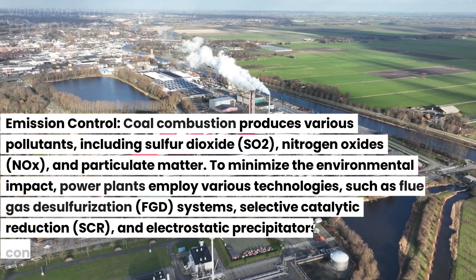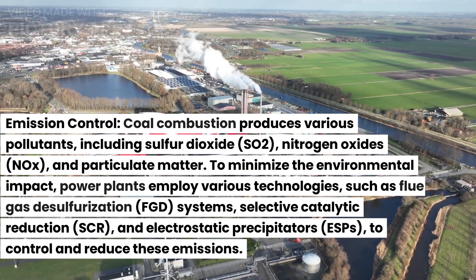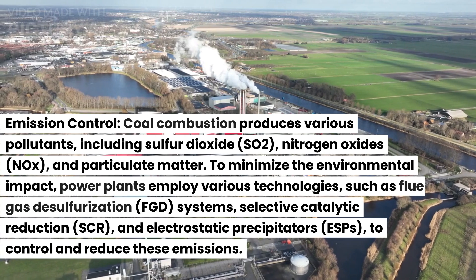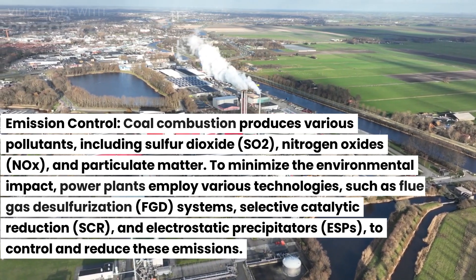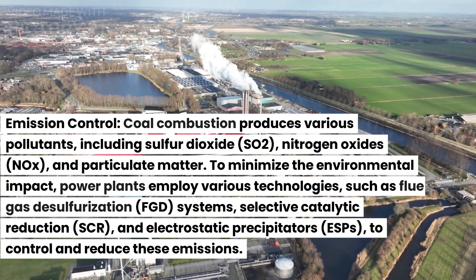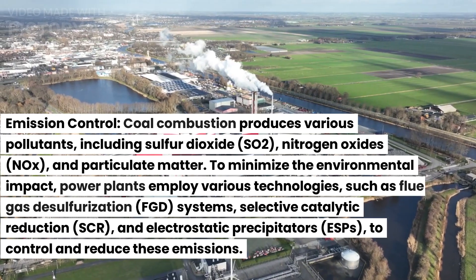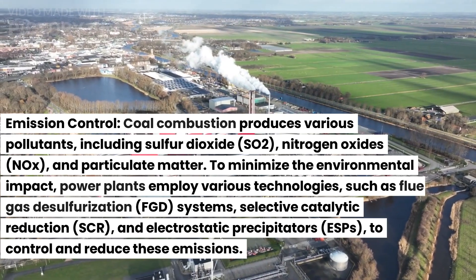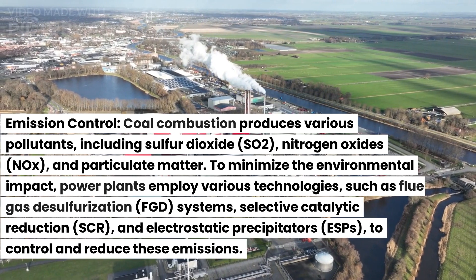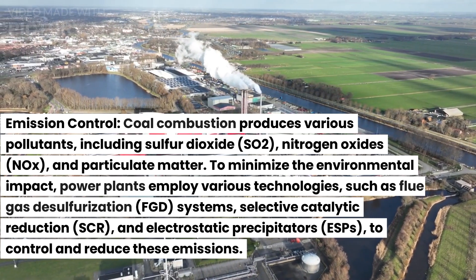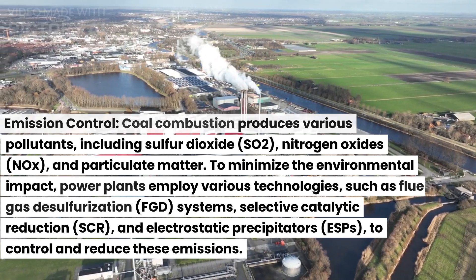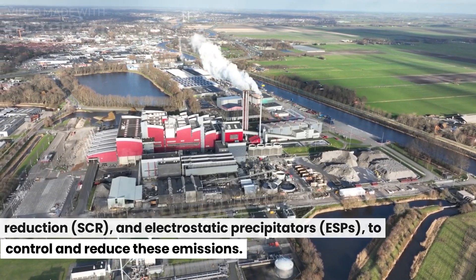Emission control. Coal combustion produces various pollutants, including sulfur dioxide (SO2), nitrogen oxides (NOx), and particulate matter. To minimize the environmental impact, power plants employ various technologies, such as flue gas desulfurization (FGD) systems, selective catalytic reduction (SCR), and electrostatic precipitators (ESPs), to control and reduce these emissions.